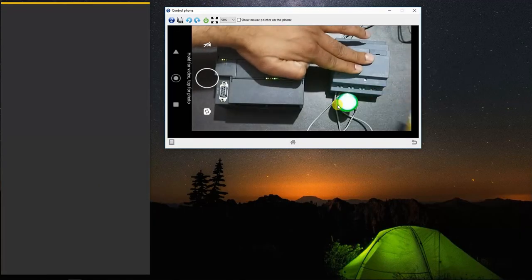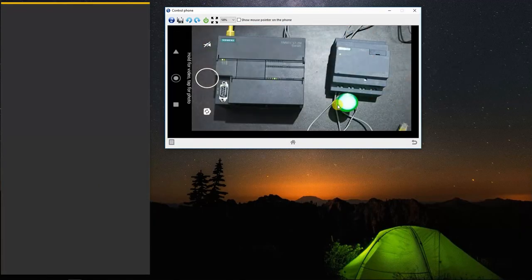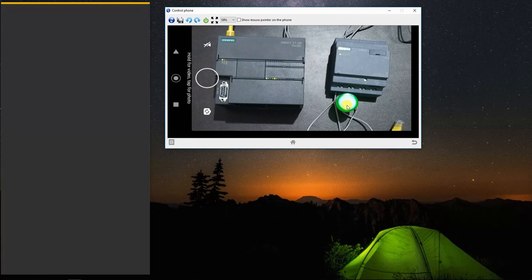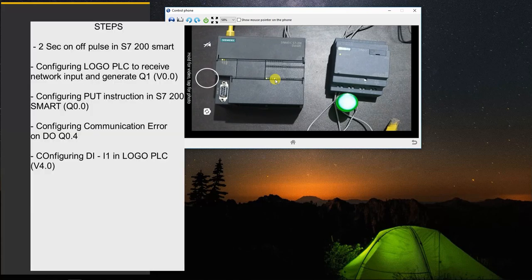Now this error LED went off and we are receiving status of DO of ST30 PLC to our logo PLC. As soon as this error is broken and this communication is broken, error LED will light up and the Q1 will hold the last status.